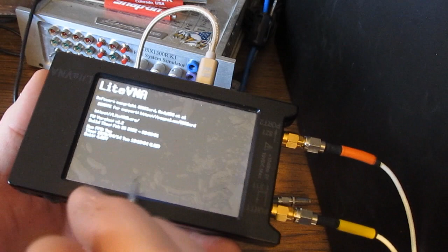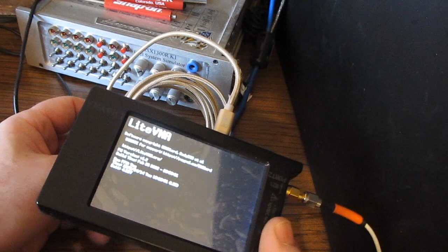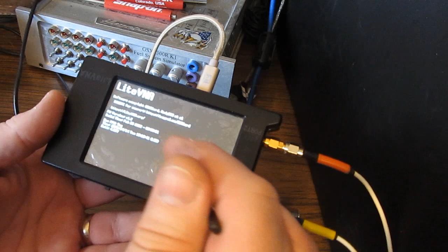So we did quite a bit of testing, and it appeared that the noise is actually being generated inside of the VNA. In other words, any filtering that we did on the USB cable had no effect. As it turns out, it behaves like the V2Plus4. Basically, the designers just didn't consider the worst case voltages for the USB bus, and what ends up happening, as I understand it, is the voltage is too high. It causes the boost converter to put out some noise that gets passed through the IF stages. So essentially what we end up doing is running this from a powered hub, and then we powered the hub from an external power supply that was adjustable. We brought the voltage down a little bit, and sure enough, all that noise cleared right up.